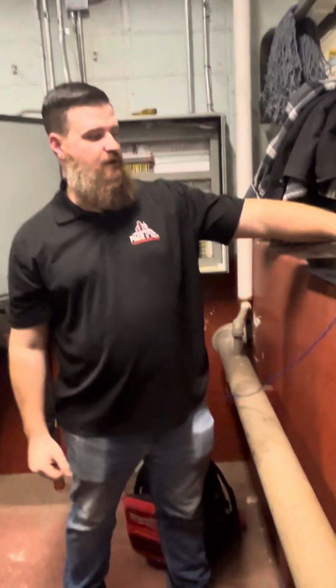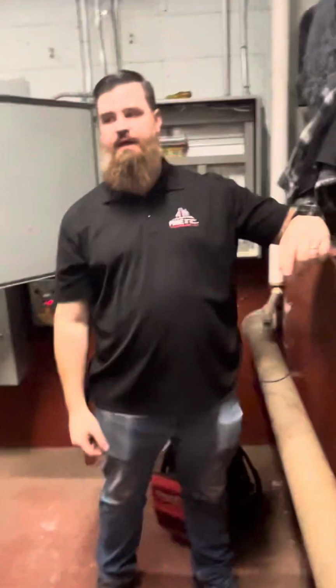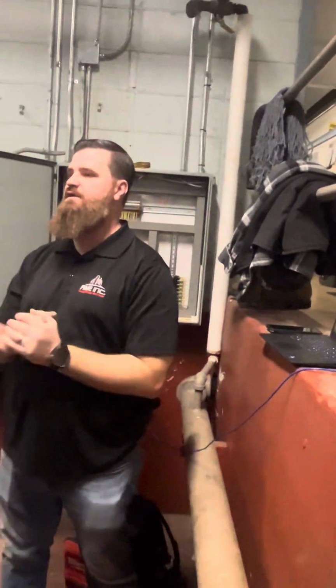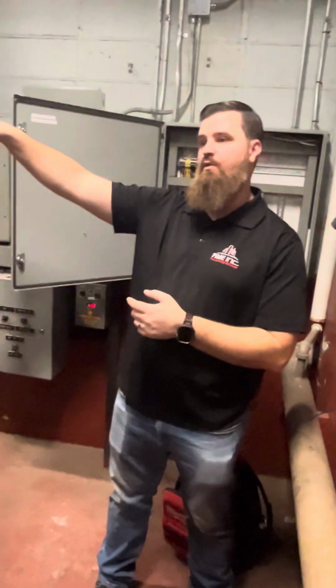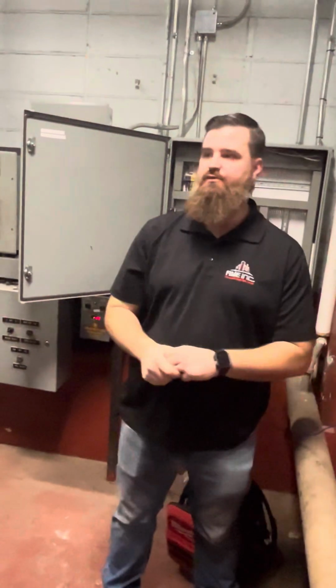Next thing, you have a system enable point. This system enable point is the master system enable. If you put that to shut down, you're shutting down everything. Nothing will operate. It doesn't mean this boiler won't operate, but it shuts down the operation of the other 3 boilers, because this is a manual switch here.